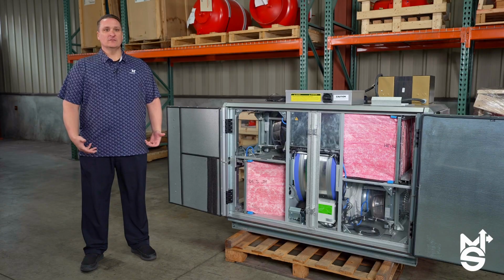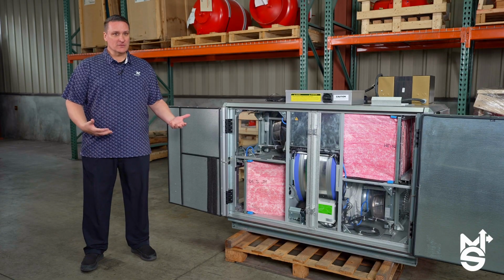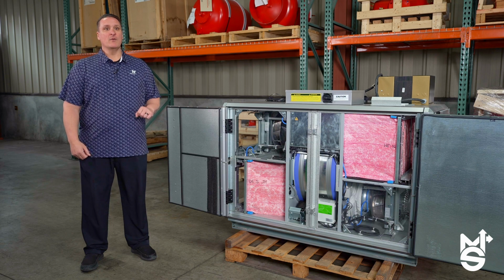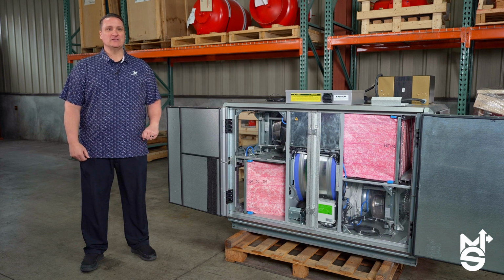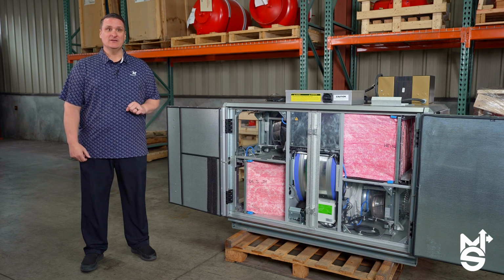How does the Swegon rotary heat exchanger benefit very high efficiency DOAS systems? The rotary heat exchanger, also known as the energy recovery wheel, is one of the highest forms of AHRI certified sensible and latent recovery in the market. Swegon engineers and manufactures their own energy recovery wheel specifically designed and patented for their energy recovery ventilators.